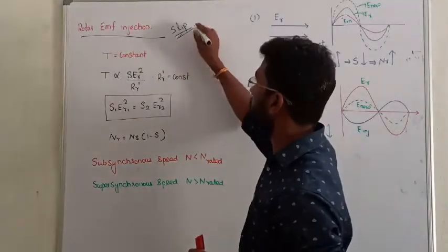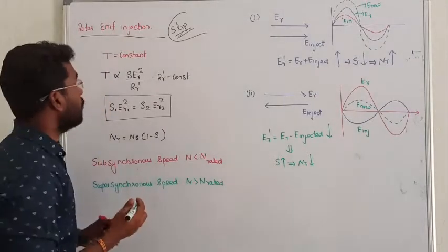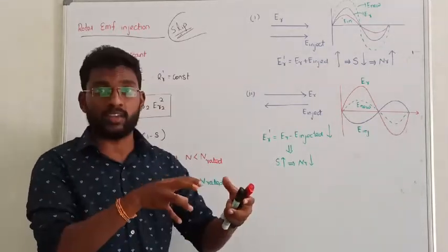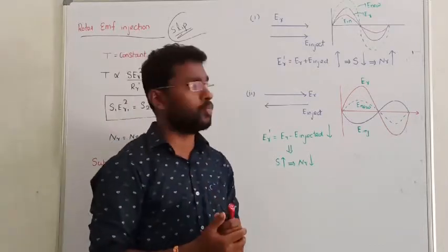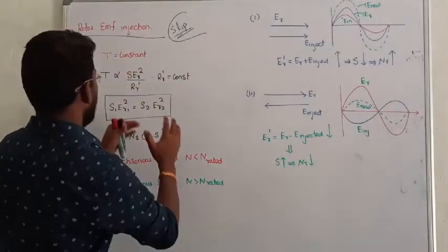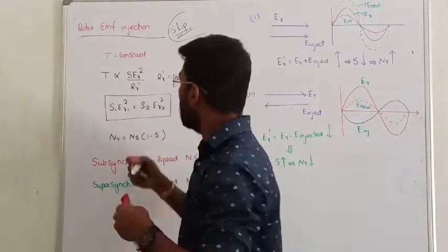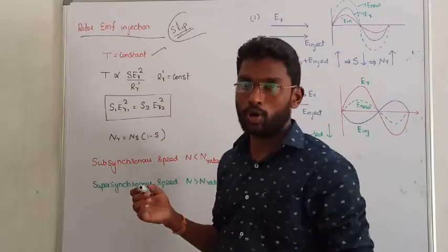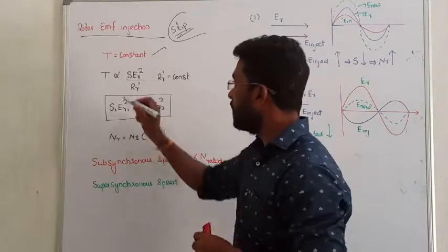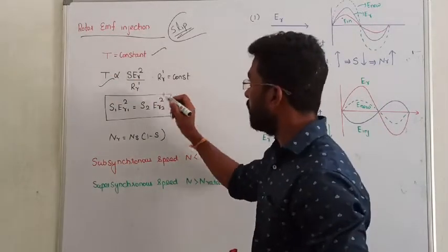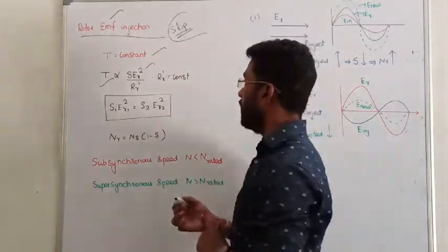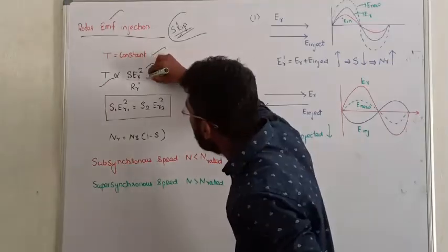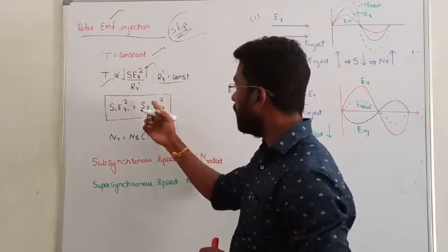In this method, we are going to inject some induced EMF into the rotor circuit to control the speed. The torque must be kept constant throughout. Using the rotor torque equation under running conditions, we are going to vary the value of injected EMF while rotor resistance stays fixed. If we increase the injected rotor EMF, slip will decrease, since both are opposite — the resultant product remains constant.